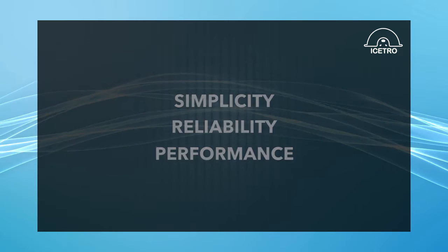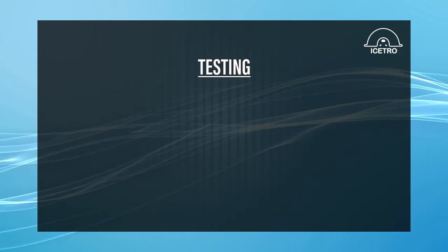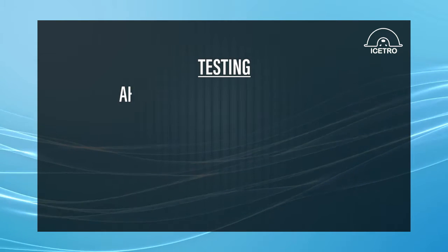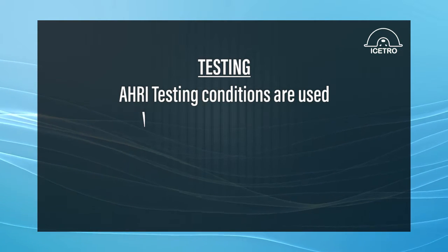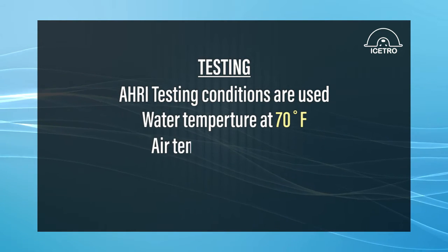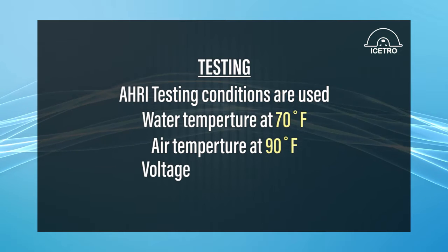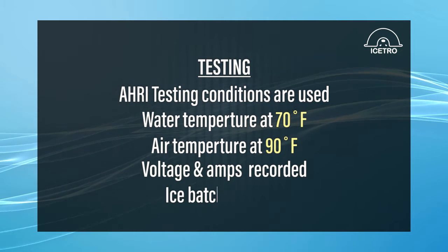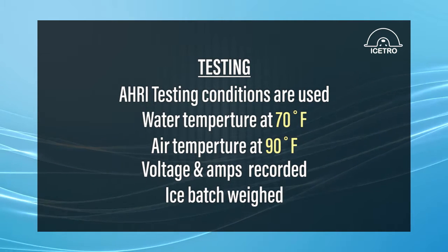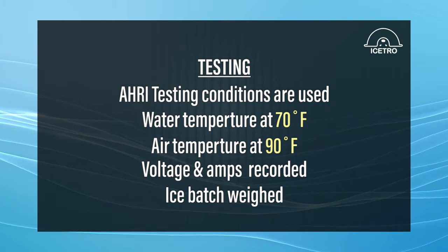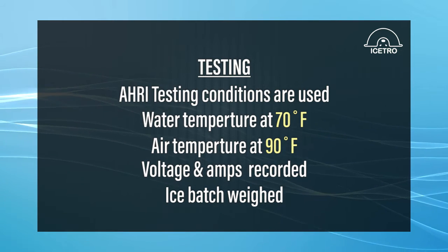All Icetro ice makers are run for three cycles prior to shipment. AHRI testing conditions are used with water temperature at 70 degrees, air temperature at 90 degrees. Voltage and amperage is recorded and ice batch is weighed. If the machine does not pass inspection and specifications, it is pulled out of production.